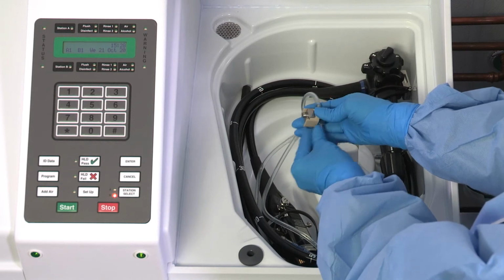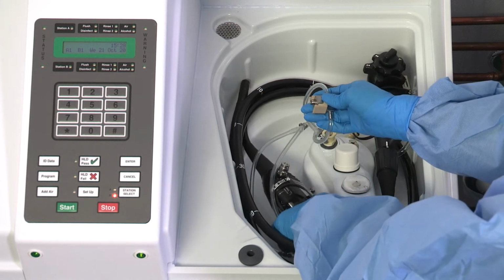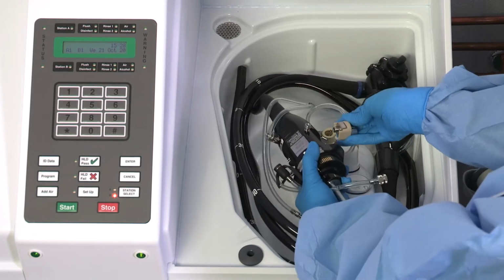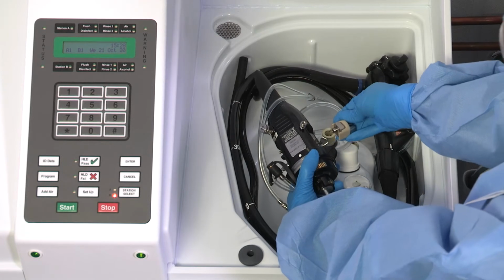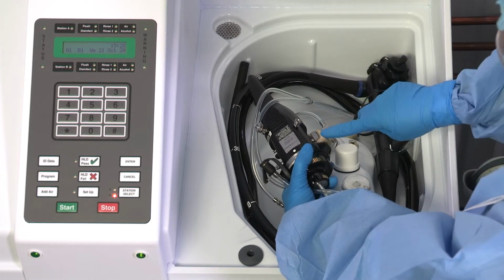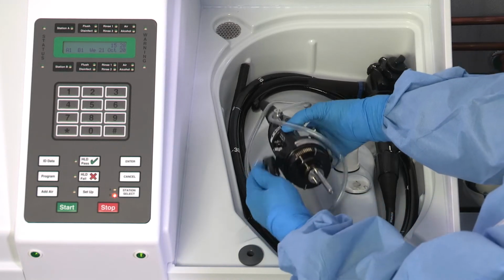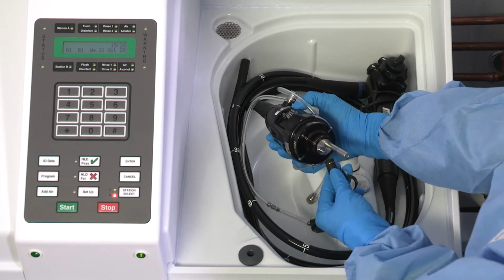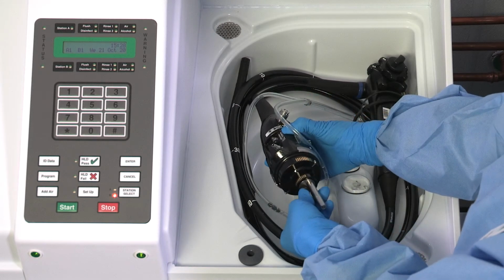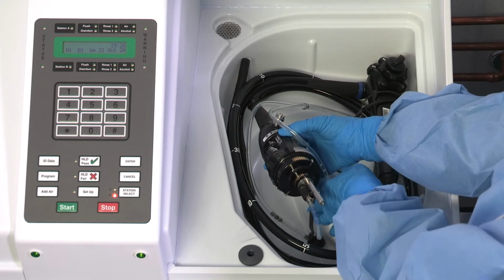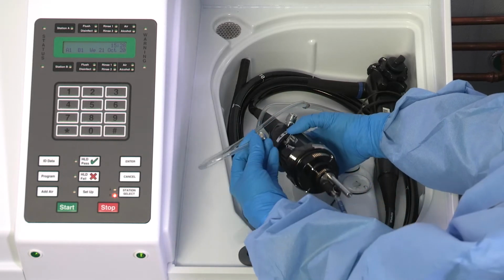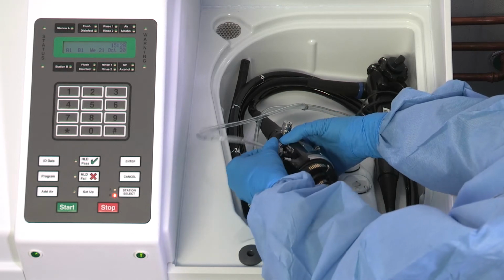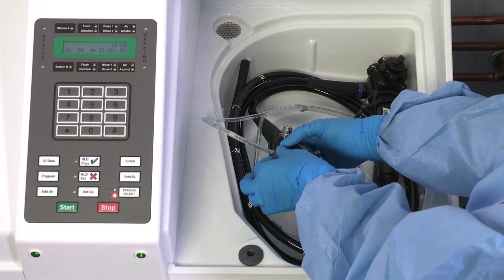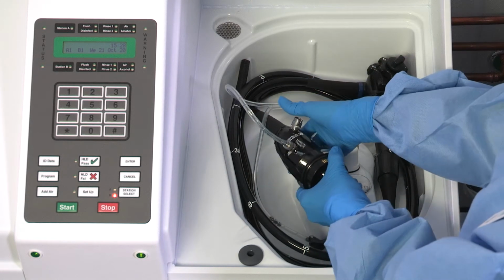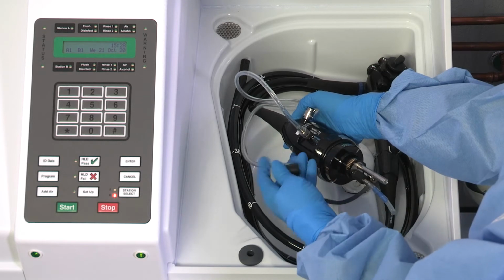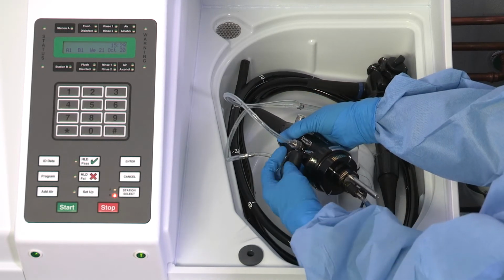Ensure the release button is pushed in. Holding the connector itself, align the connector openings with the air-water ports on the endoscope. Push the connector onto the ports until the latch moves out and you hear an audible click. Tug lightly to ensure the connector is attached securely. To attach the air probe connector, align it with the air pipe on the endoscope. Push and slide until fully engaged. To attach the auxiliary water connector, align it with the endoscope's fitting and turn clockwise until fully engaged. To install the suction connector, align it with the suction barb and push onto the barb until fully engaged.